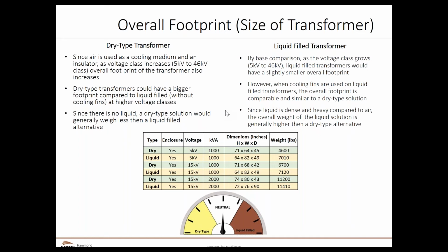So it's kind of neutral. It will depend upon the situation. It will depend upon if it's indoor or outdoor. It will depend upon the temperature rise and overload capabilities of that particular application in order for you to decide which may have an advantage or not. You really have to get more into the details to figure out ideally which one would have the smaller footprint. It's not always apparent.